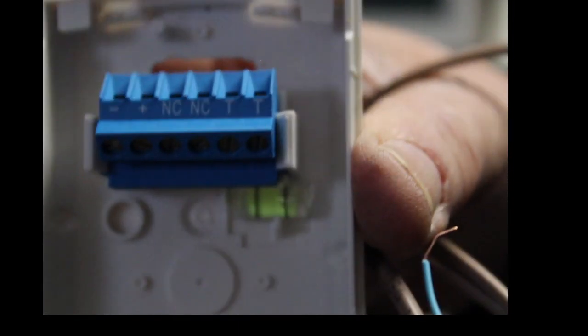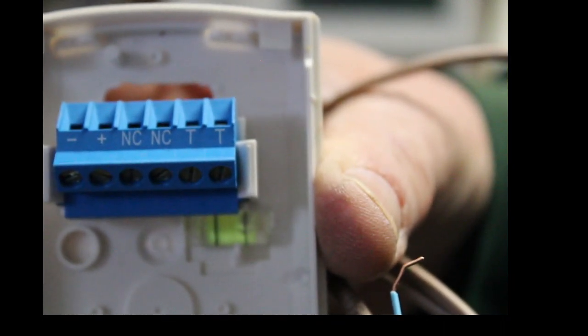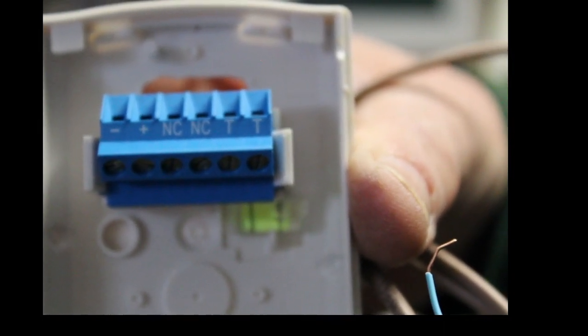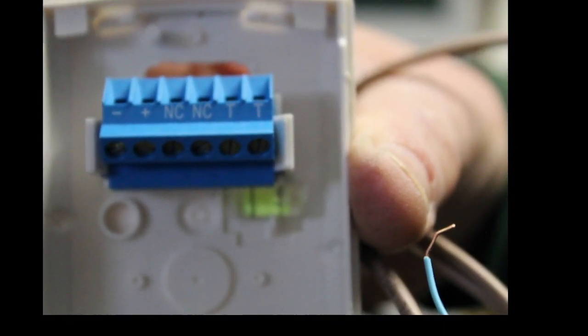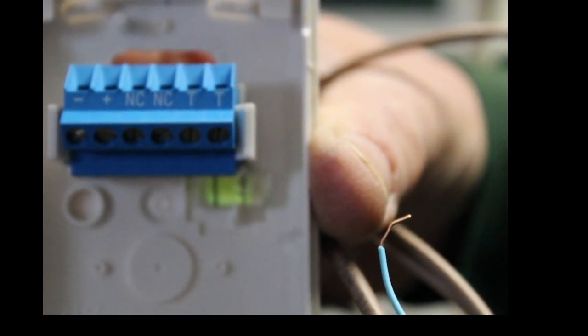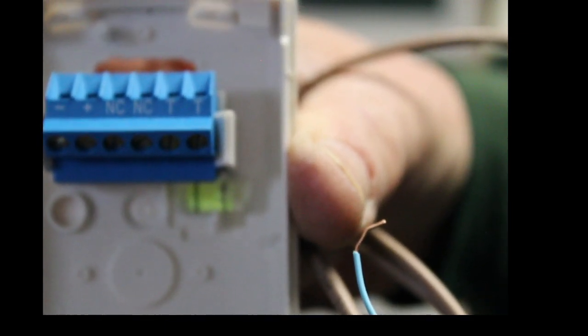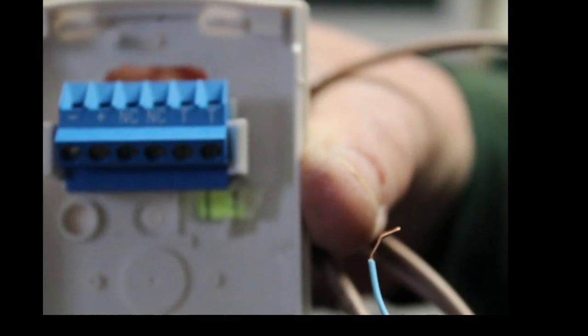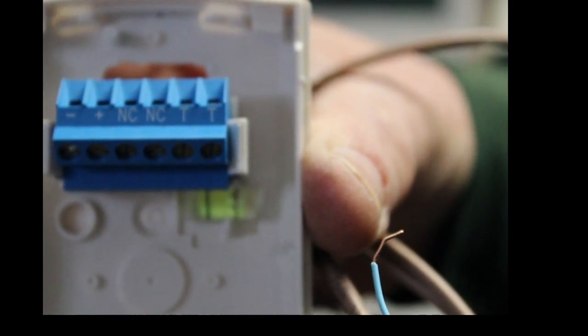And on this motion detector, the negative is going to be black. The positive is going to be red. And when it says NC-NC, that can be where your yellow and blue go. It doesn't matter where the yellow or where the blue goes, as long as your yellow and blue goes into the terminal marked NC, which is normally closed. The TT, don't worry about that. That's tamper.